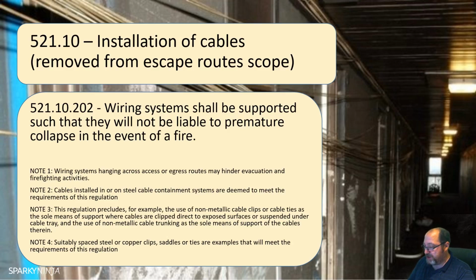Non-sheath cables for fixed wiring shall be enclosed in a conduit, ducting, or trunking. This requirement does not apply to a protective conductor to 543. This is a protective conductor running on its own. Non-sheath cables are permitted if the cable trunking system provides at least a degree of protection of IPXXD or IP4X, and if the cover can only be removed by means of a tool or a deliberate action. So this is something I've often picked up on a periodic inspection and in the EICR. So if you have non-sheath cables, so you have singles in a trunking or in a conduit or something, it says there with the installation of cables, if they're in a trunking system, it must be to IPXXD or IP4X.